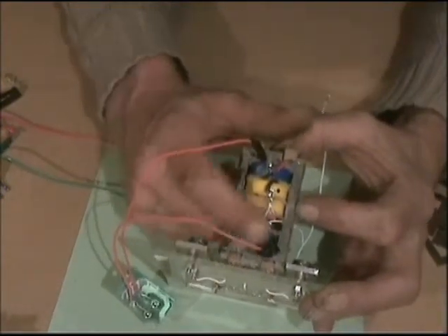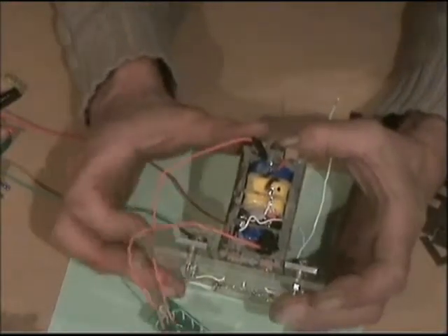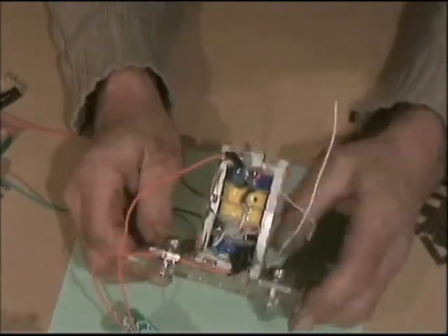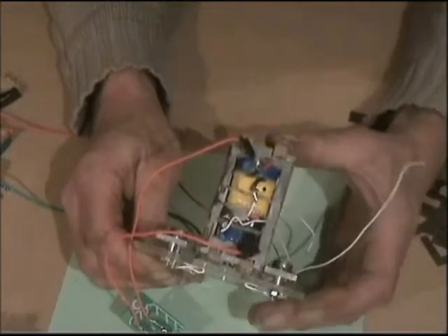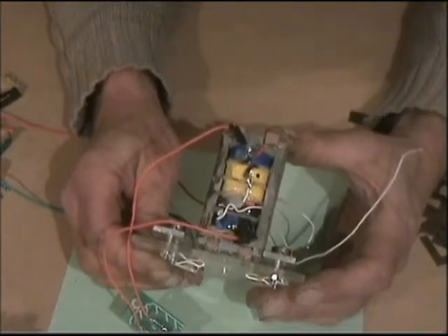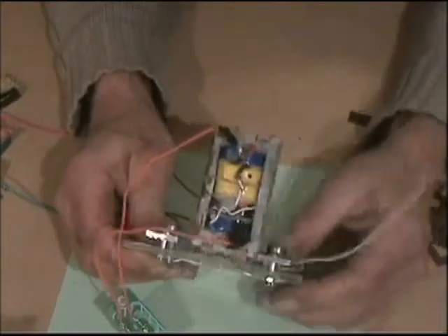So you've got no problem with wiring. You could test it separately by pulsing the primary and see which way the needle moves. But I just go for that method. I've done that and given it a go. If you don't get the necessary results, you can always swap the wires over.